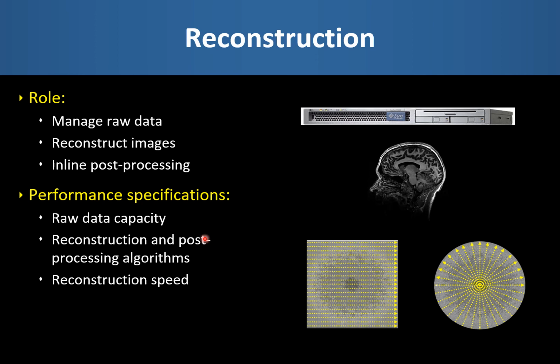Some of the performance specifications we should be looking at are the capacity to hold large volumes of raw data, certainly transiently. We do not routinely store or archive raw MRI data, only the reconstructed images. There should be a range of reconstruction algorithms available, including not only conventional Cartesian or line-by-line acquisitions that we've looked at previously, but the increasing use of non-Cartesian trajectories, such as this radial acquisition, where the data will require regridding onto a regular grid prior to Fourier transformation. The reconstruction and post-processing speed is governed by whatever hardware processors are incorporated into the system, and as we said, with the increasing use of machine learning and deep learning algorithms, a number of these cutting-edge reconstruction systems are now GPU based.